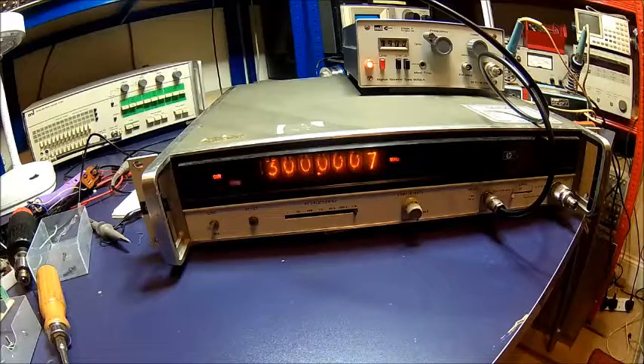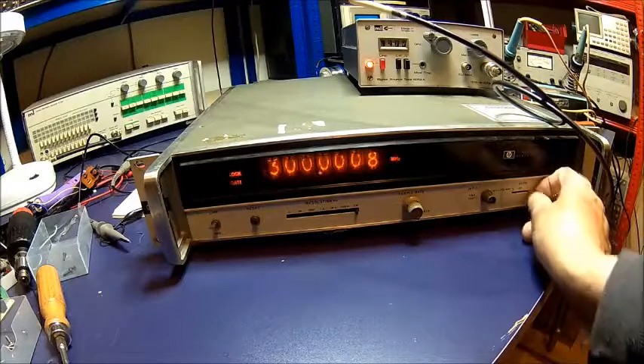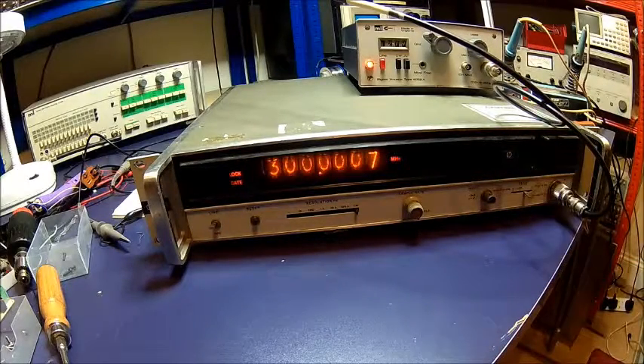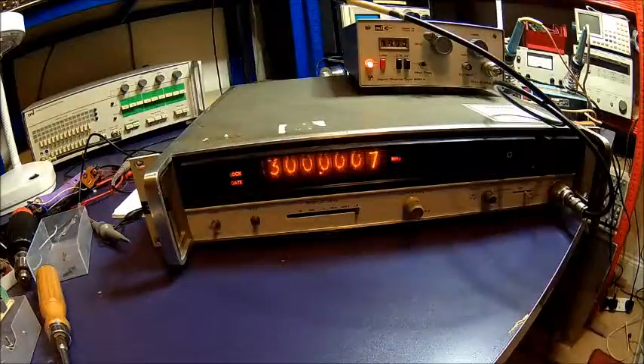Shame that the high frequency part doesn't work, but at least we got some spare parts for the other one. It seems everything on the baseband counter is working, just the heterodyne part is not working, and I've been there before. It's a lot of work to get it right. There's many checkpoints and calibration points, but if it works, it's a really nice counter because you don't need to mess around with these harmonics as you normally do with this one here.